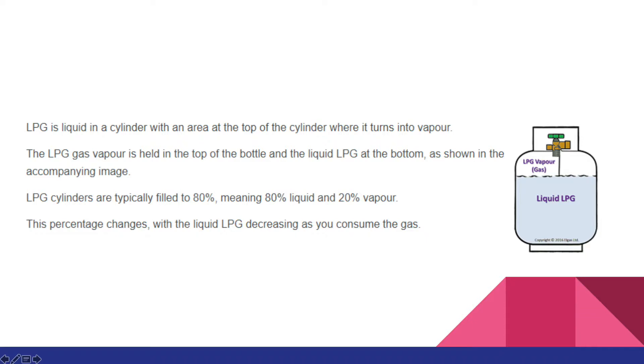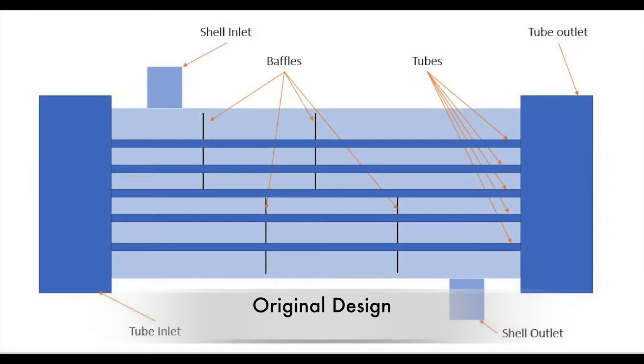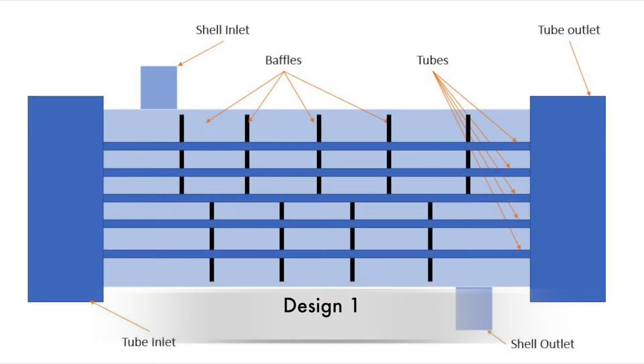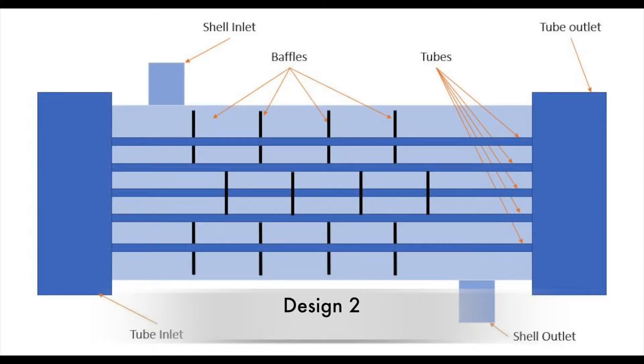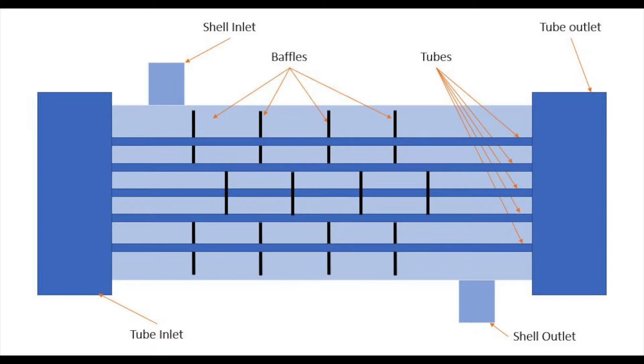For an LPG cylinder, the contents need to exist as 80 percent liquid and 20 percent gas. This is the original design for the heat exchanger that the company provided us, and this is the modified design. We added straight baffles and increased the number of baffles. For the second design, we changed the geometry to a donut-hole style and also increased the number of baffles.